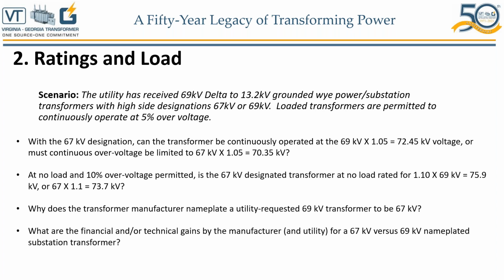A transformer cannot be 67 or 69. It has to be either or. So I'm going to have to assume that. And I know that it's not a reconnectable condition or anything like that, because the voltages are extremely close. So I'm going to assume that we're talking about, let's say, a 69 or a 67 kV, maybe two different transformers, and I'm going to answer your questions going forward.